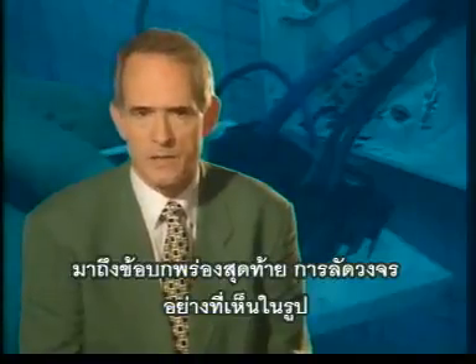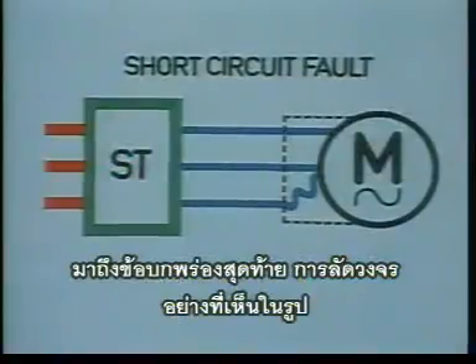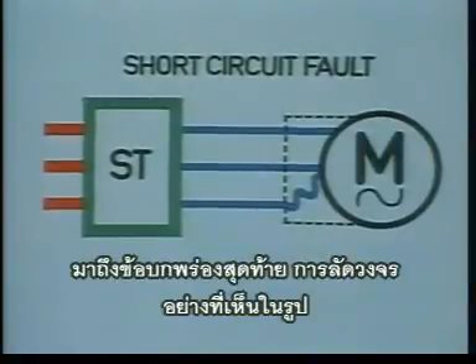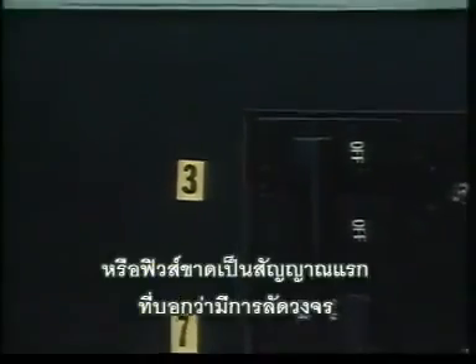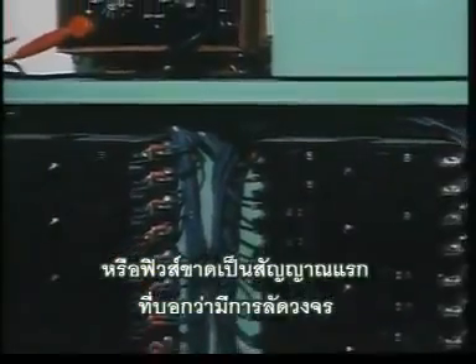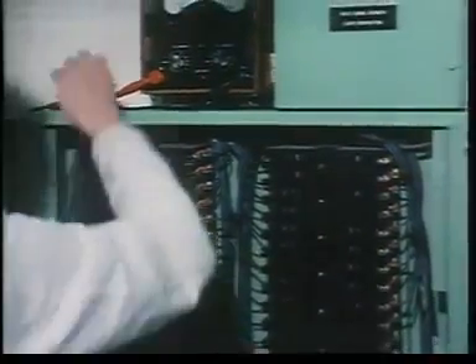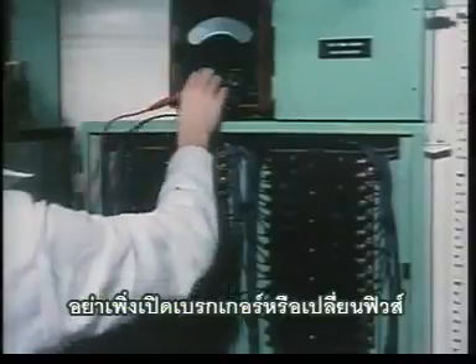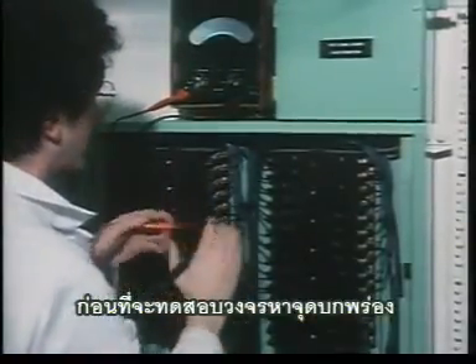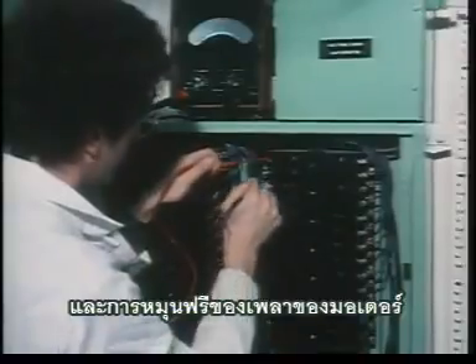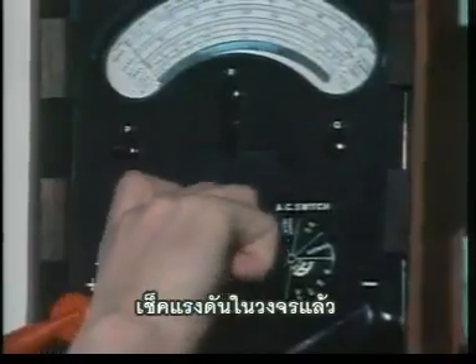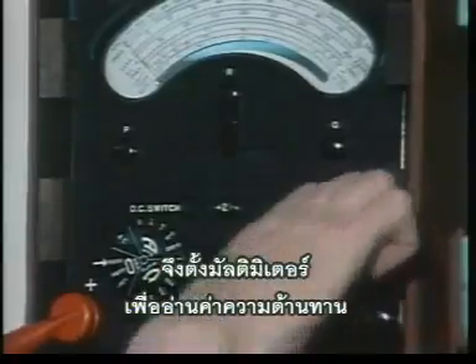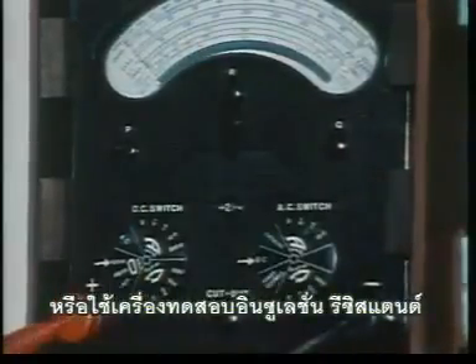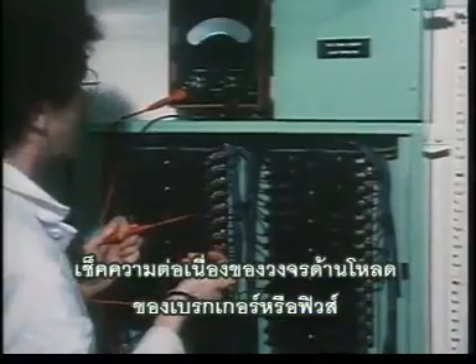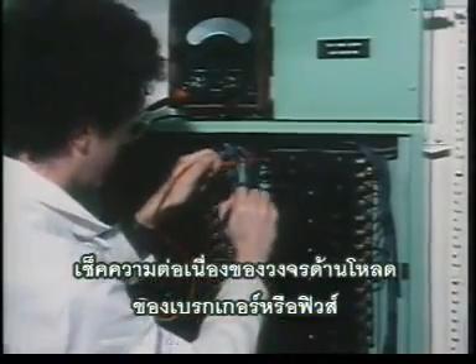This brings us to our last distribution fault, which is a short circuit fault, shown on this drawing. A tripped circuit breaker and blown fuses are usually the first signs that a short circuit fault has developed in a circuit. Do not reset the breaker or replace fuses before testing the circuit for electrical faults and the mechanical freedom of motor shafts. Check the circuit for voltage, then reset the multimeter to read resistance, or use an insulation resistance tester and check the circuit continuity at the load side of the circuit breaker or fuse.